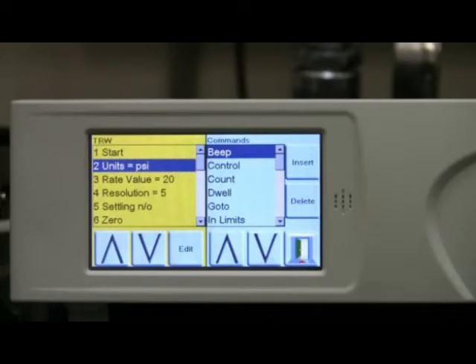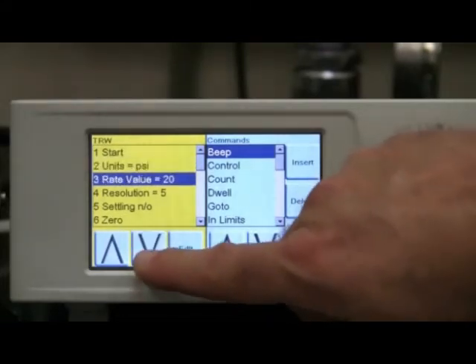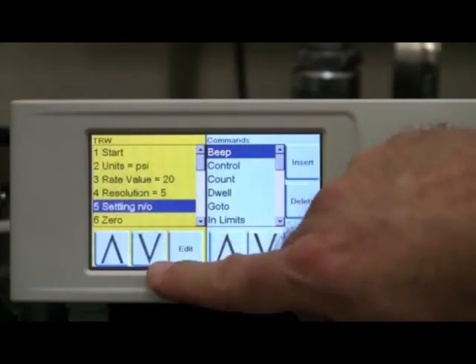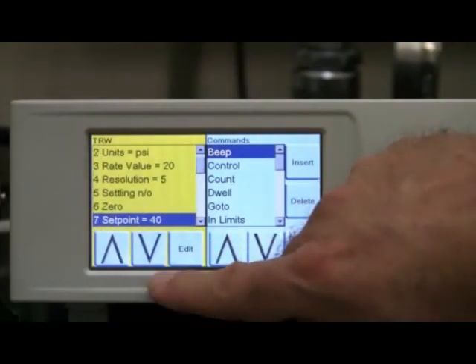Each program can have multiple steps and perform various functions. For example, in this program, the units are first set to psi, the control rate is set to 20, the pressure resolution to 5 digits, and the slew rate to no overshoot. The unit will then perform a zero before controlling to the first set point, which is 40 psi.